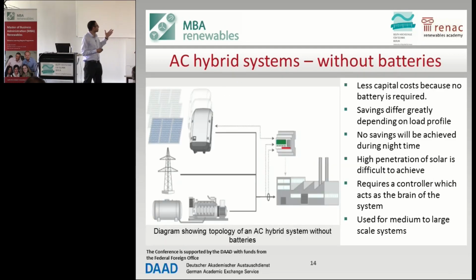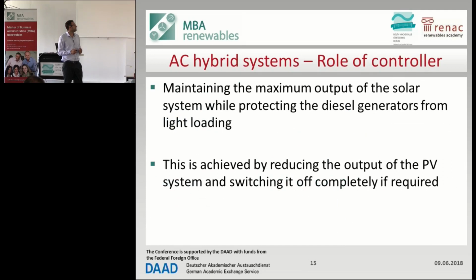Now, the controller, which is here, I forgot to mention it. Again, the guys talked about it yesterday. It has one very important task: maximizing the solar system while protecting the diesel generator from light loading. That's the most important. That's the line that you should not cross in these systems. You should not go below 30% or 40%, depending on the manufacturer of the diesel generator. You should not operate in light loading.